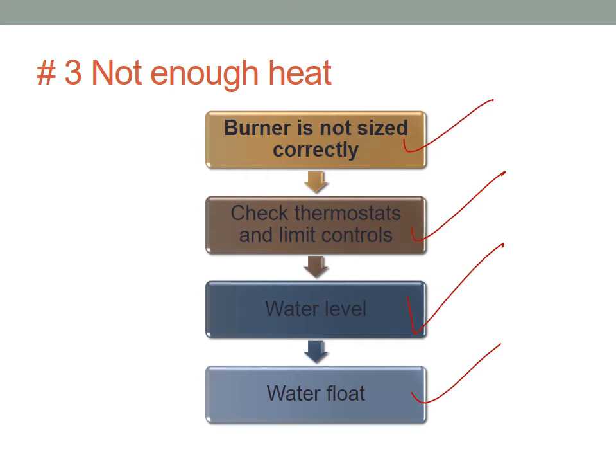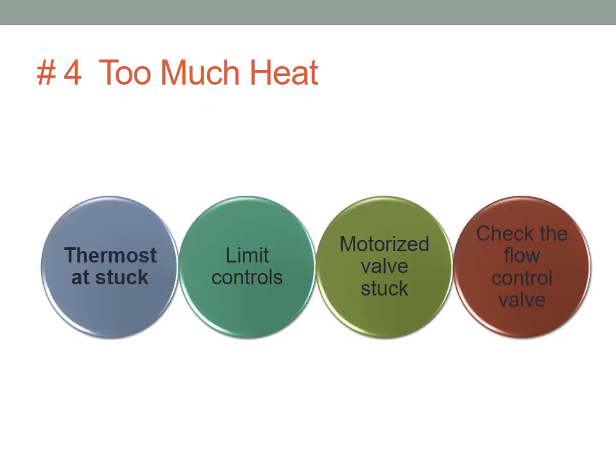Too much heat. Thermostat is stuck or misreading. Limit control done the wrong way. The motorized valve is stuck. So if we have too much heat, we're letting too much hot water come in, or hot air or steam. So it could be something with your control. It's got to be a control problem. Check the flow control valve again for water flow.